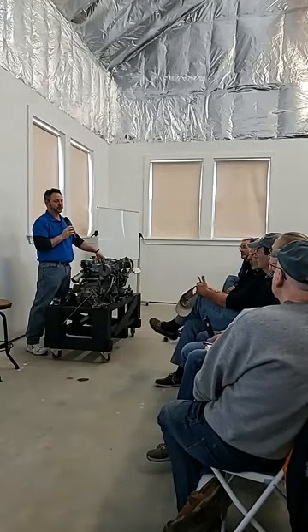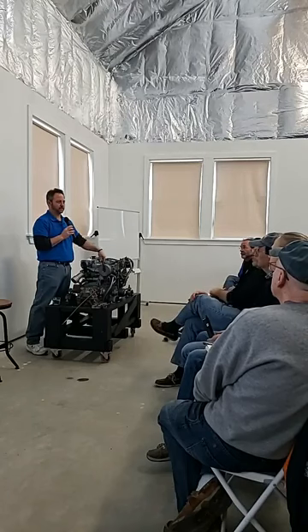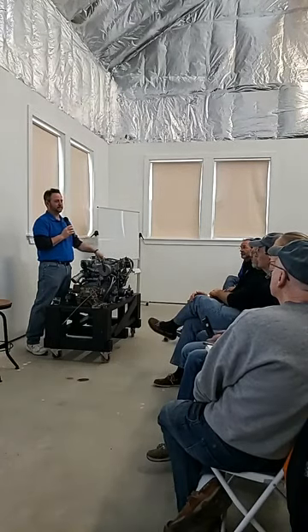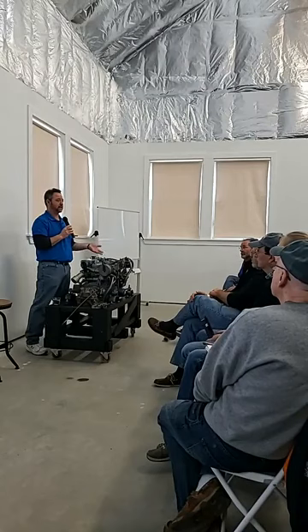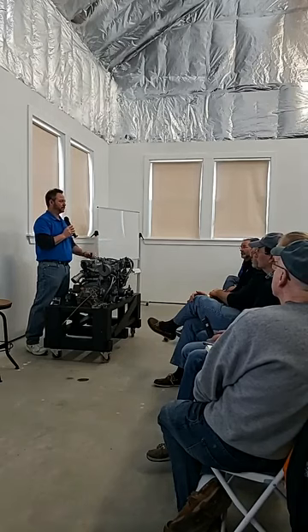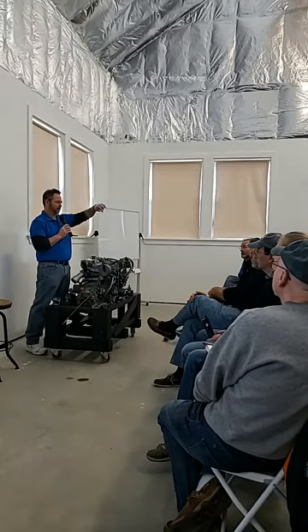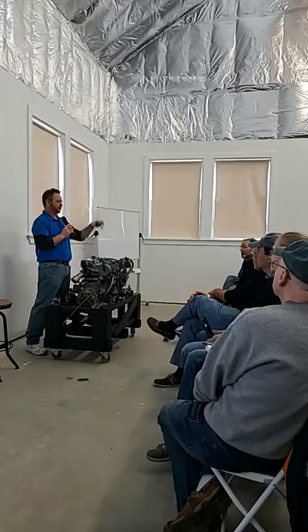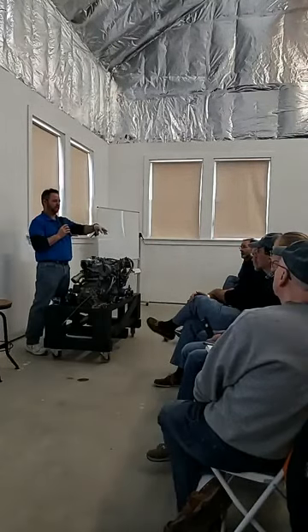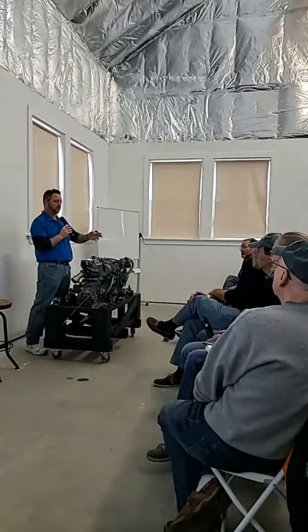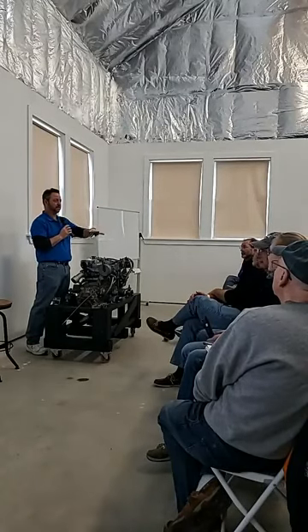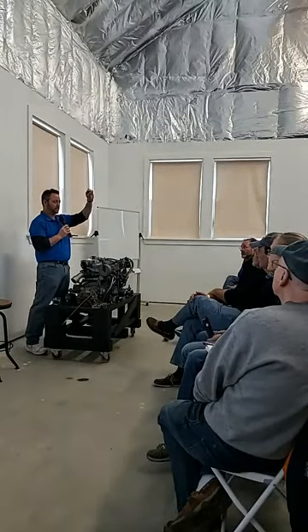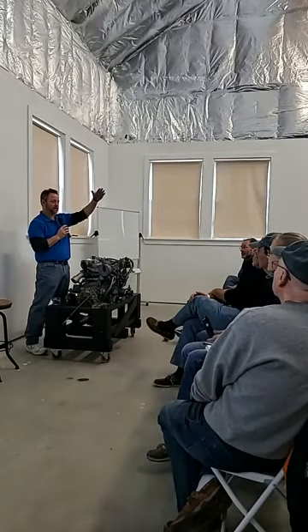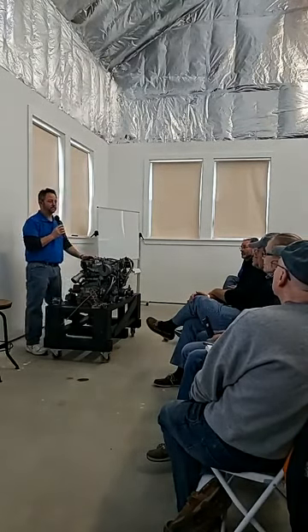And if you do get into that, are you going to have to bleed the system? It depends on the design of your Racor and how it's laid out. If you have the 500 series, 900 series, or 1000 series, no, you won't have to bleed it unless you drain the whole unit down. But if it's a style with the T-handle on the top and the lid comes off, you can just pull the filter out, put the new element in, replace a couple of O-rings, have some spare fuel, top it back up, and put it all back together. The air will purge out just by adding fuel at the top, so you won't have to bleed those.